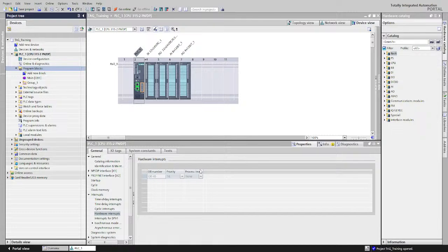But if you have that block, like I said, it will capture that error and ensure that it does not stop the PLC. It can be giving you the warning, but the error is still there. You can configure errors as minor and major. You can configure that this error should not stop the system. Minor errors cannot stop the system; the system will keep on running. But major errors will actually stop the system from running. So you must be able to differentiate between those two.